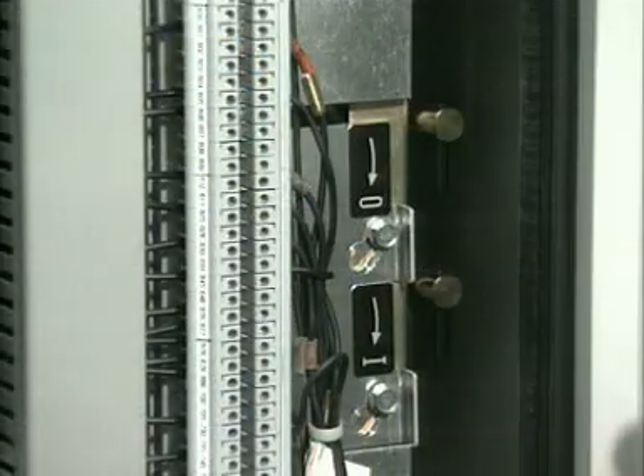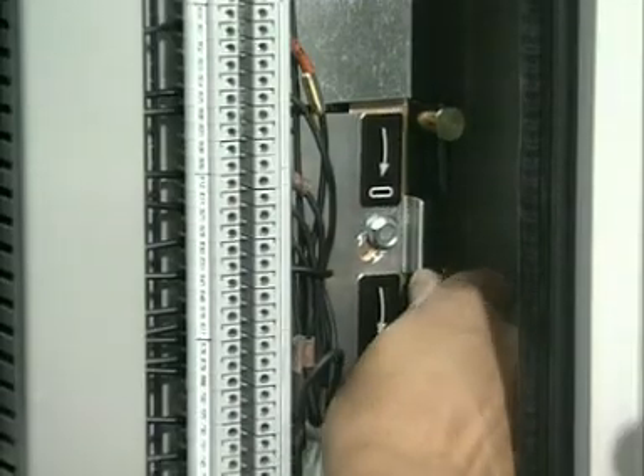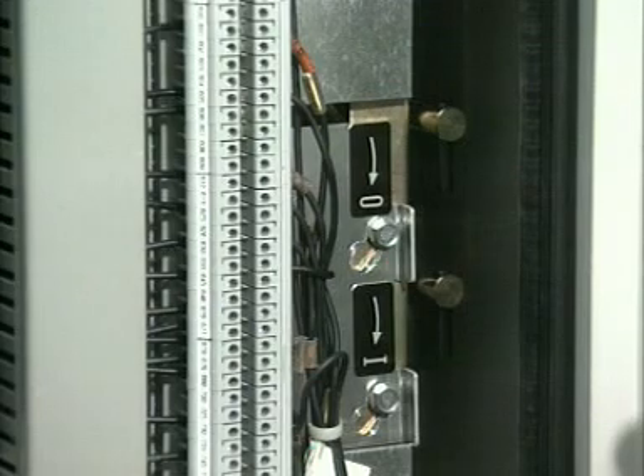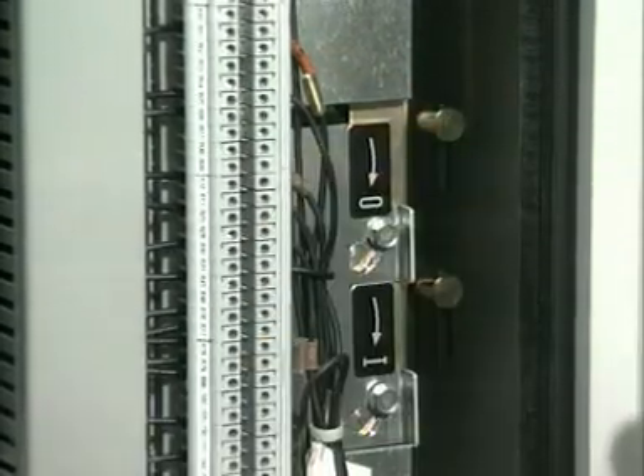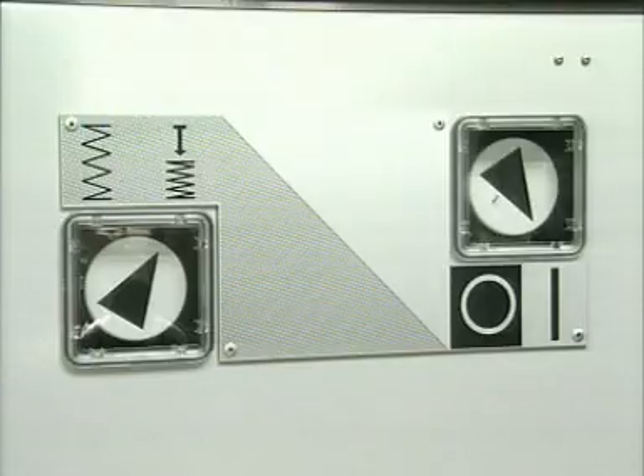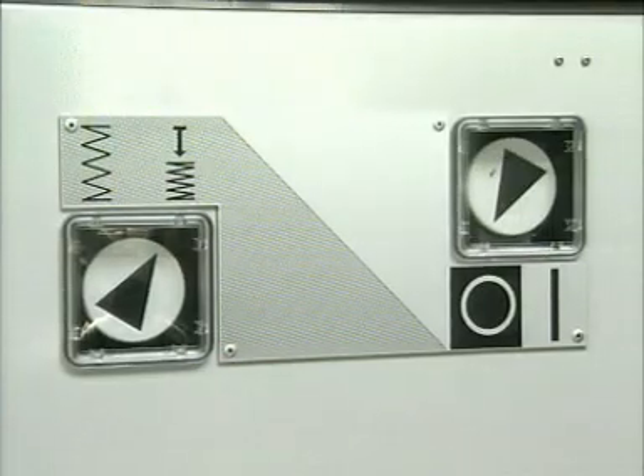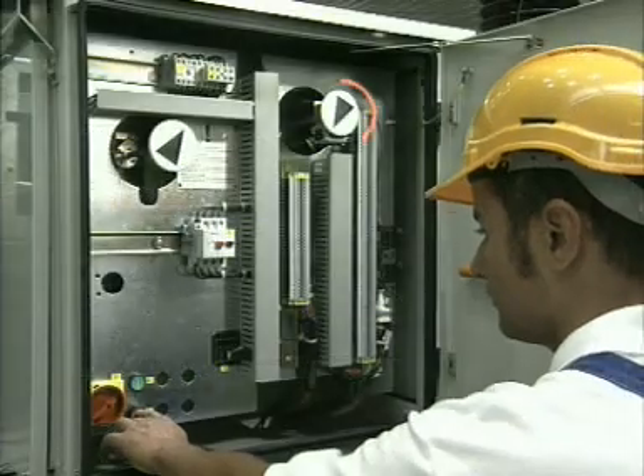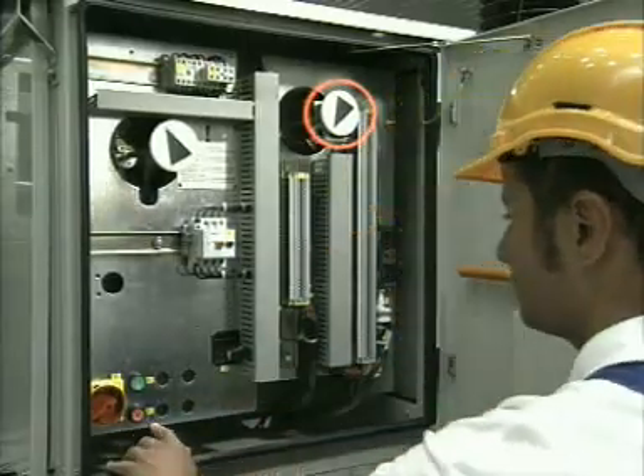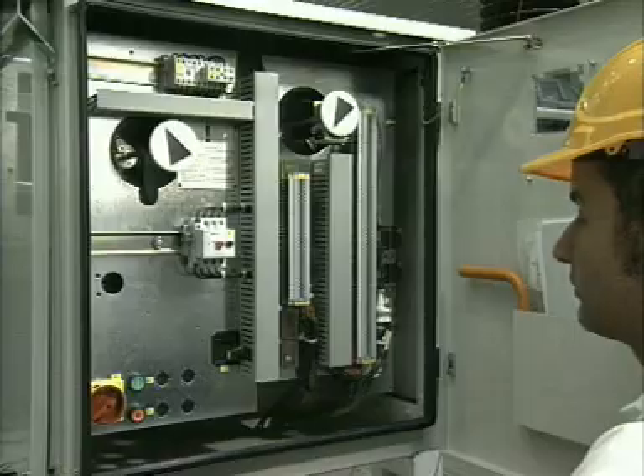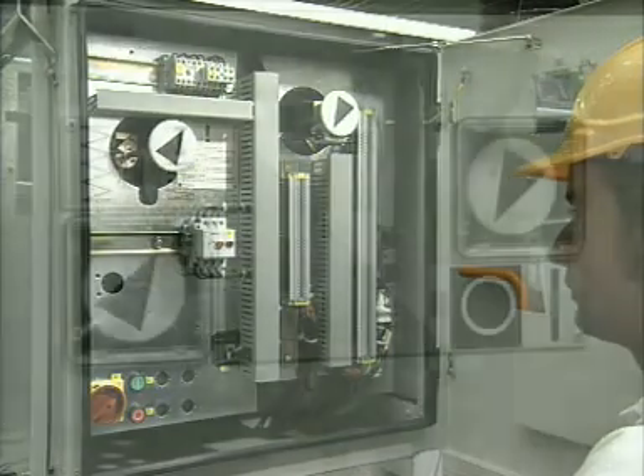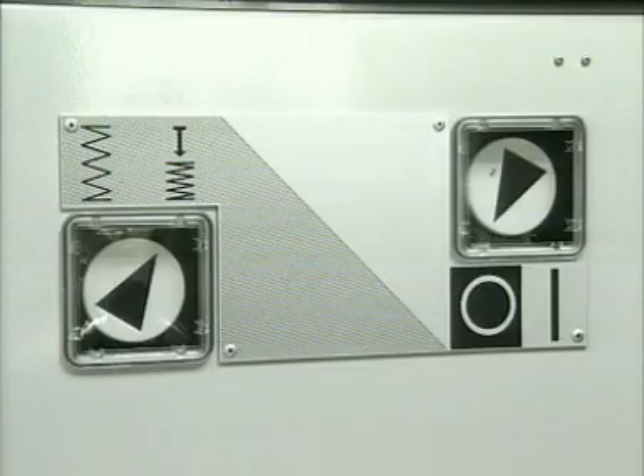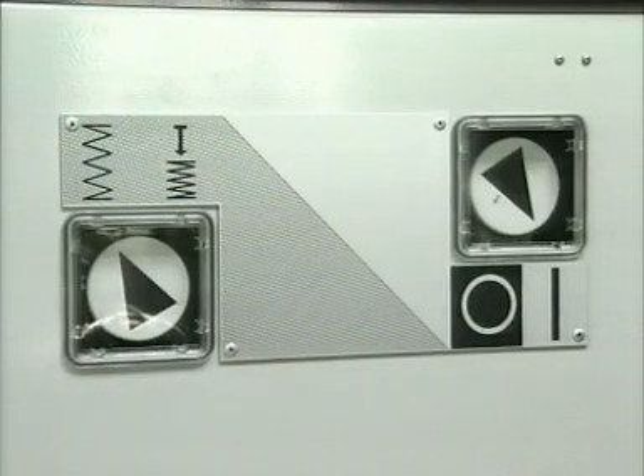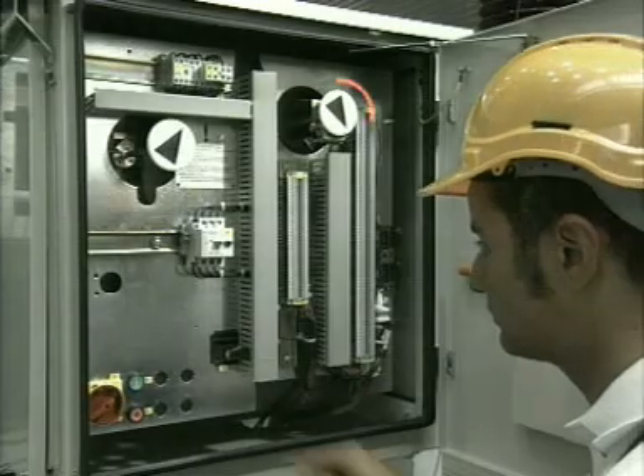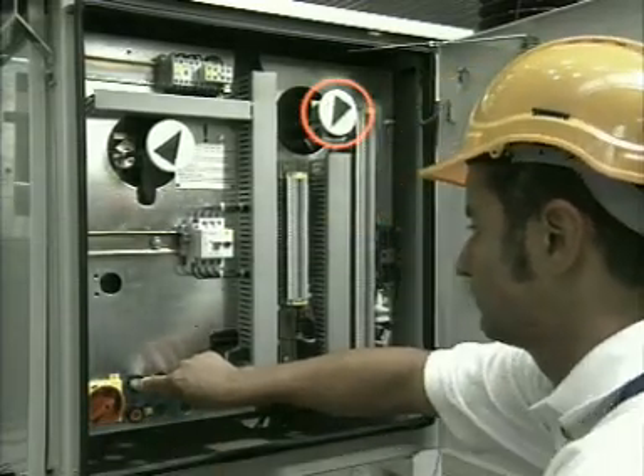Run a function test of manual control by carrying out 1 manually triggered closing operation and 1 manually triggered opening operation. To check the anti-pumping system, first move the breaker to the open position. With a continuous open command and an additional closing command, the breaker should carry out only 1 closing and 1 opening operation. Then move the breaker to the closed position. With a continuous closing command and an additional opening command, the breaker should carry out only 1 opening operation.